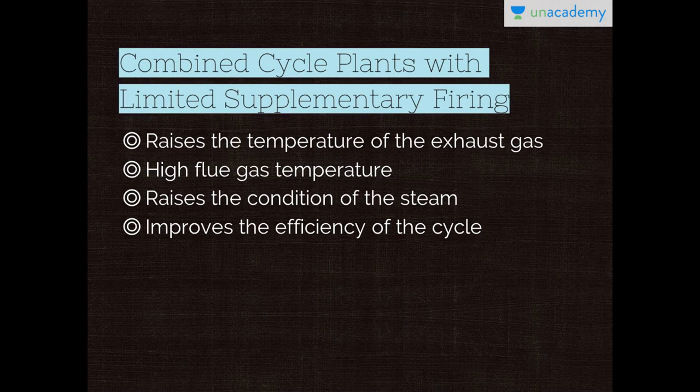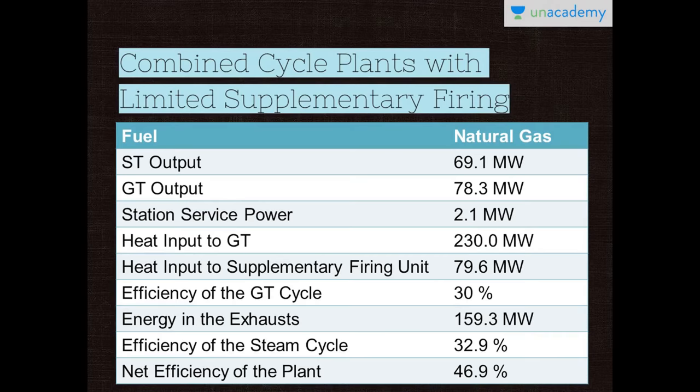Let's move on to the combined cycle plants with limited supplementary firing. Supplementary firing raises the temperature of the exhaust gas to 800 to 900 degrees centigrade. Relatively high flue gas temperature raises the condition of the steam to 84 bar, 525 degrees centigrade, thereby improving the efficiency of the cycle. I have given a table which is the example of a combined cycle plant with limited supplementary firing. The fuel used is natural gas.